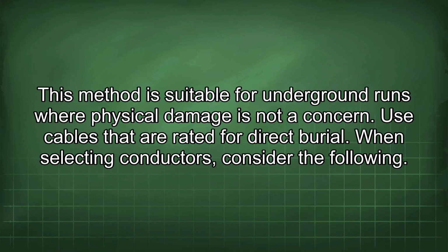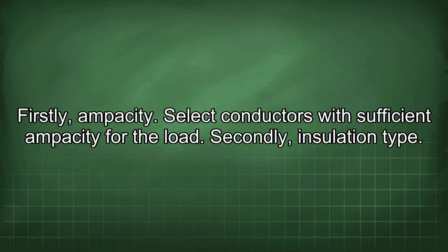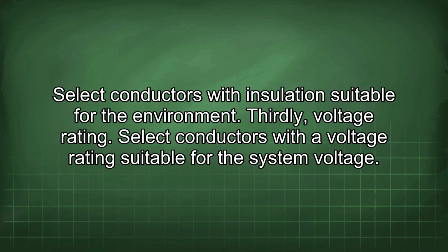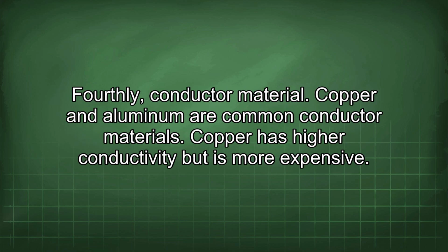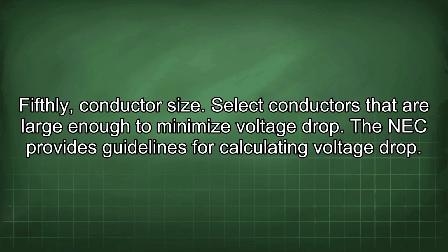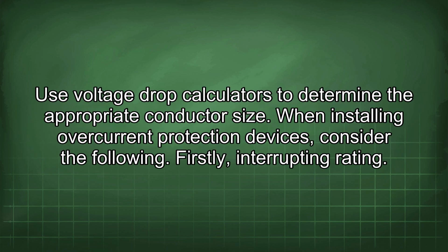When selecting conductors, consider the following. Firstly, ampacity. Select conductors with sufficient ampacity for the load. Secondly, insulation type. Select conductors with insulation suitable for the environment. Thirdly, voltage rating. Select conductors with a voltage rating suitable for the system voltage. Fourthly, conductor material. Copper and aluminum are common conductor materials. Copper has higher conductivity but is more expensive. Fifthly, conductor size. Select conductors that are large enough to minimize voltage drop. The NEC provides guidelines for calculating voltage drop. Use voltage drop calculators to determine the appropriate conductor size.